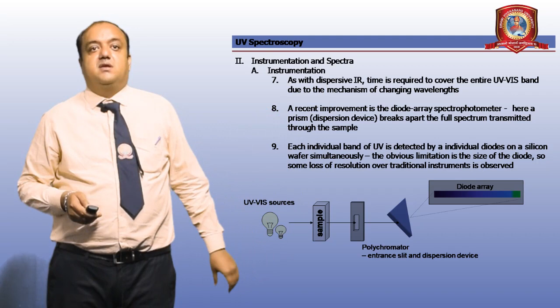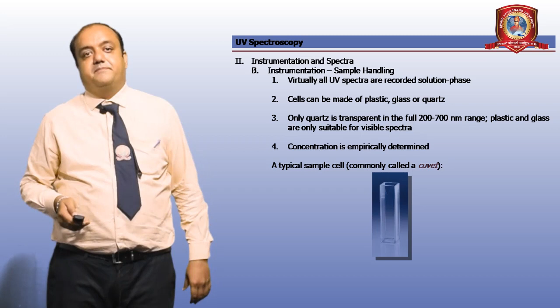Sample handling. Virtually all UV spectra are recorded in solution phase. Cells can be made of plastic, glass or quartz. Only quartz is transparent in the full 200 to 700 nanometer range. Plastic and glass are only suitable for visible spectra. Concentration is empirically determined. This is a typical sample cell, commonly called a cuvette.